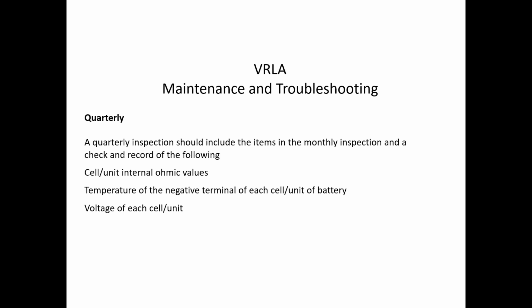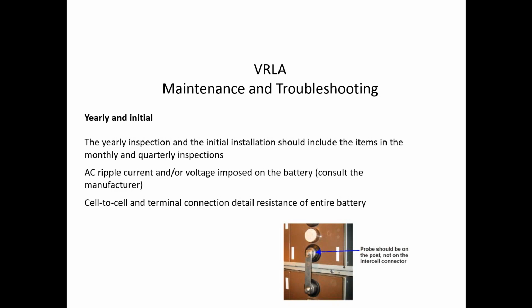But like I said, you have to look at the whole picture. And more often than not, we use those values as triggers for capacity testing or load testing. That's because those meters, and those companies hate when you call them meters, because hey, these are test sets. So those testers are okay. They're certainly better than not doing anything, and they give you an idea of what's going on. I would never hang my hat and recommend a battery replacement or bless a battery for performance based strictly on those readings.